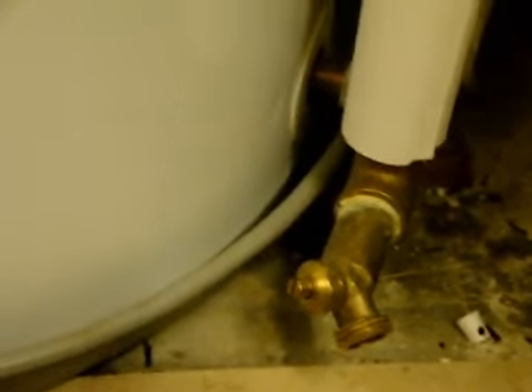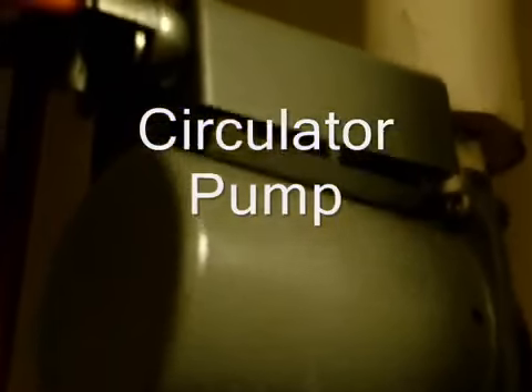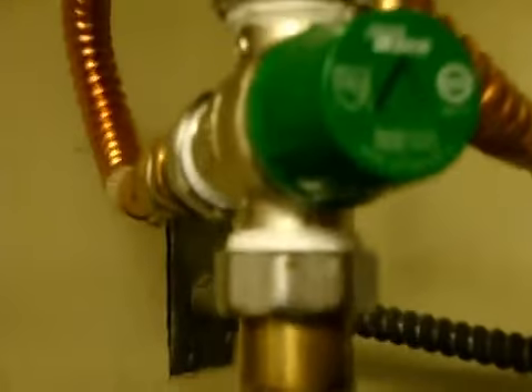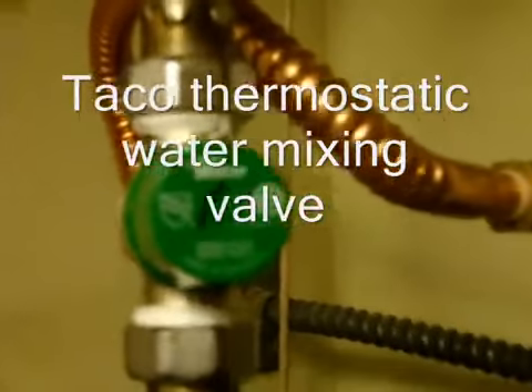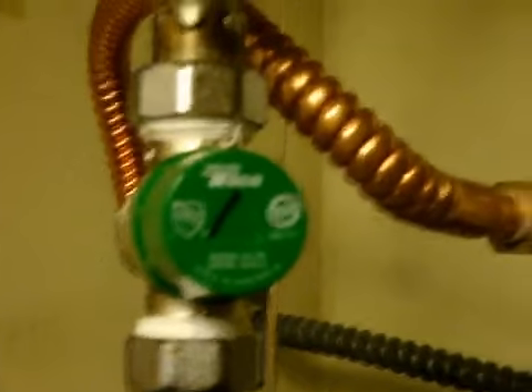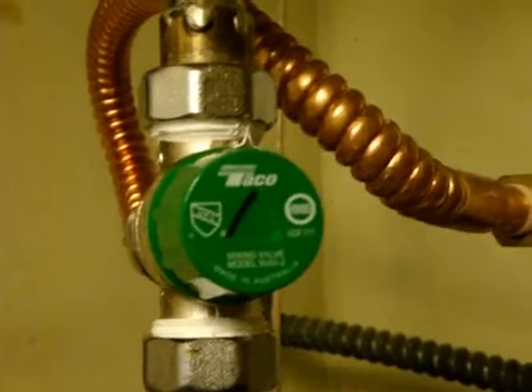And here's how the system works. There's a heat exchanger up in the attic, and down here at the bottom, where you have your drain, is the coldest area of the tank, and it goes up. Here's a circulator pump circulating the water through a heat exchanger up in the attic, and then back down into the cold side of the standard water heater, and then it comes out on your hot side like normal. I had to install a mixing valve because it was so hot, and I have this set to 130 so nobody gets hurt.